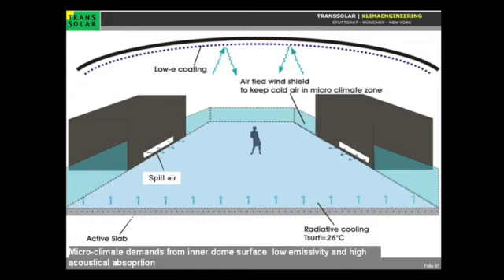The Louvre in Paris made a demand: if we were using electricity produced in Abu Dhabi by gas turbines to cool outdoor spaces, and that became news in French newspapers, we'd be in serious trouble. So it was clear all this energy had to come from renewable sources. Finally, the building got a large geothermal system. The problem with a geothermal system in Abu Dhabi is that the mean annual temperature is 28 Celsius.